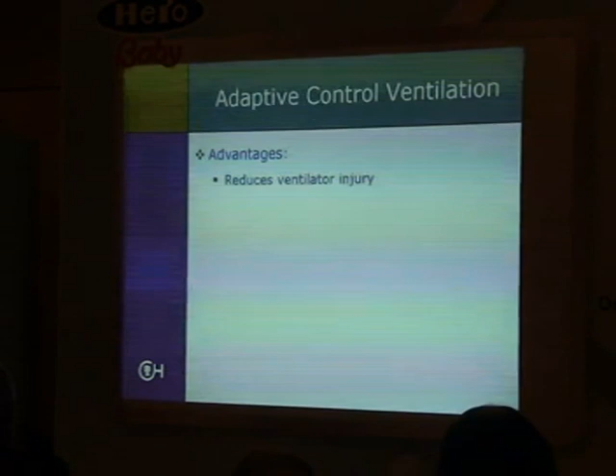The disadvantage of this mode is that it relies on accurate exhaled tidal volumes to be measured. So you have to have an airway flow sensor in line with the baby, and it needs to be working correctly. There's a lot of things that cause problems with airway flow sensors, whether it's secretions or humidity, the airway leaks. If your airway leak is too much, then you're not getting an accurate measure of the tidal volume from the flow sensor because it's coming out the mouth. So then these modes won't work very well.